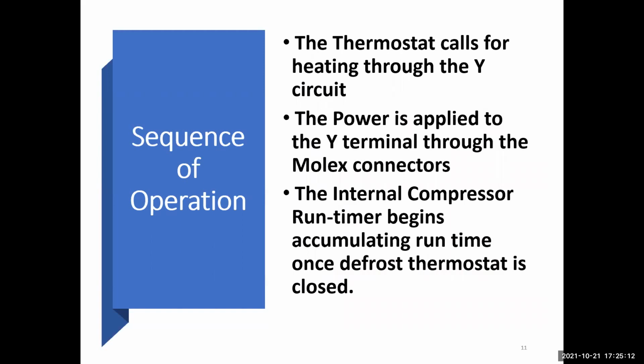There must be a continuous 24 volts AC to terminals R and C. So the sequence of operation: the thermostat calls for heat through the Y circuit. The power is supplied by Y terminal through the Molex plug. The internal compressor timer begins accumulating time once the defrost thermostat is closed.